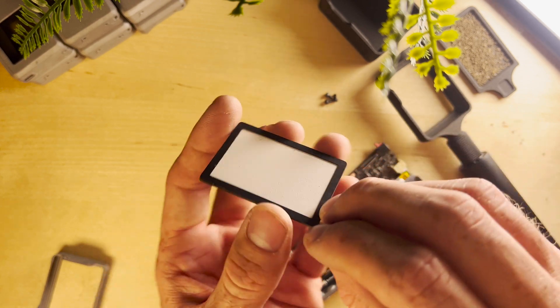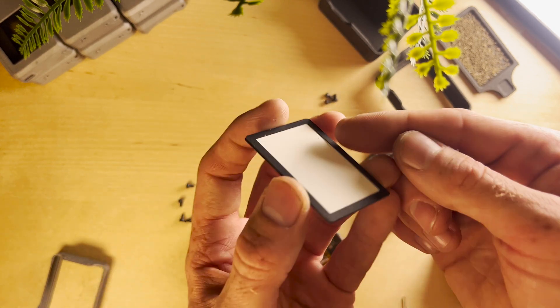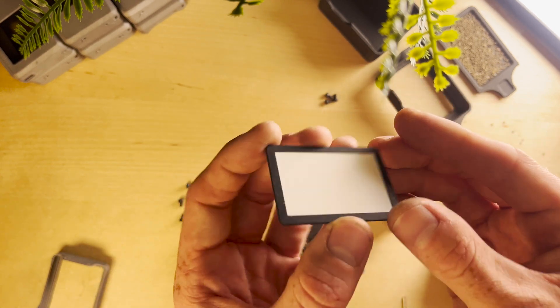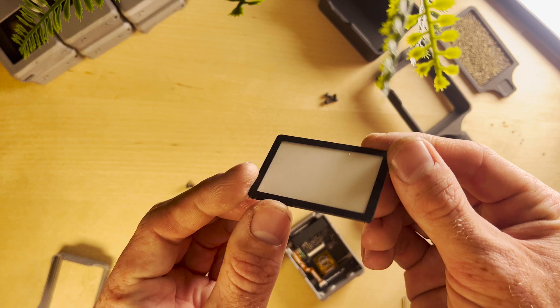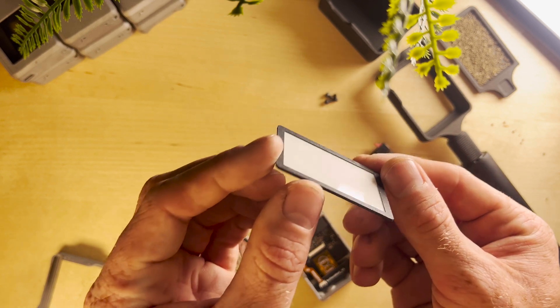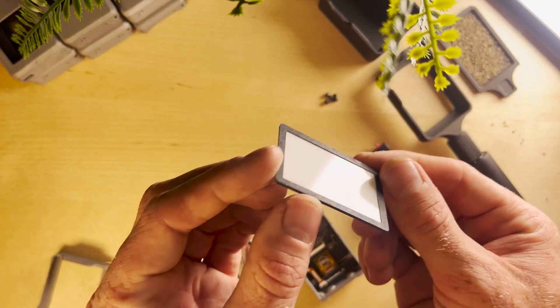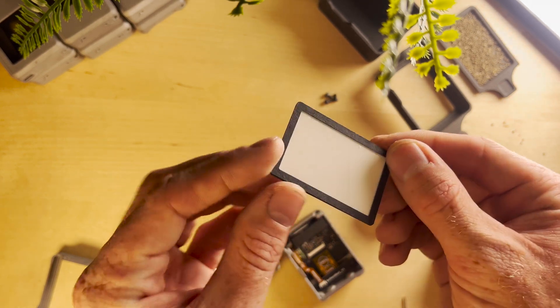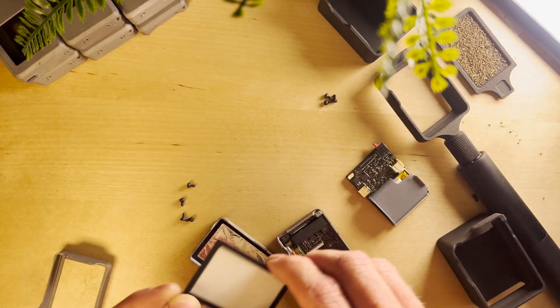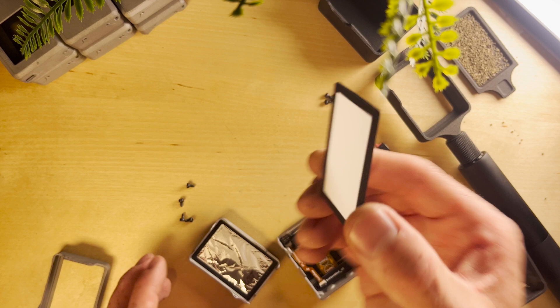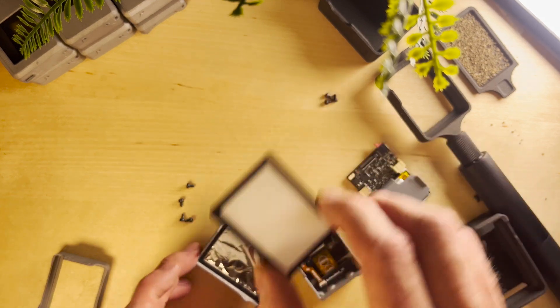We also have our alpha beta scintillator. With the alpha beta scintillator make sure there's one side that is not reflective and then there is a side that is reflective that's more glossy. Make sure that glossy side is pointing up. The matte side is what detects the alpha particles.